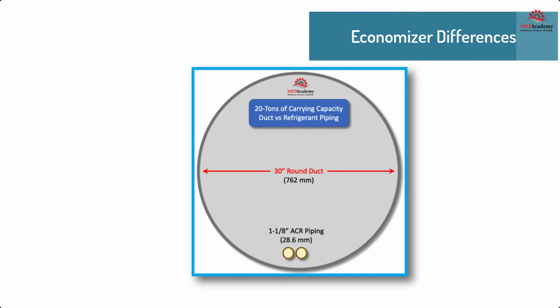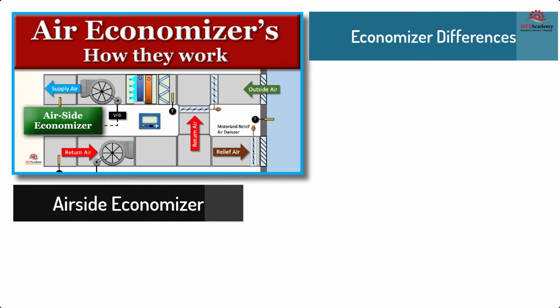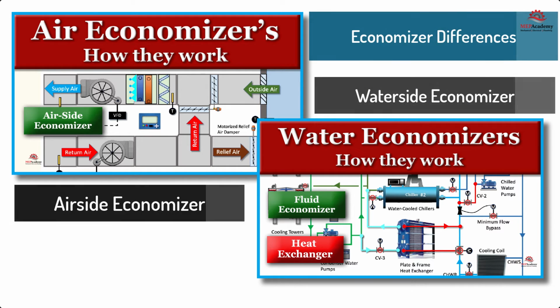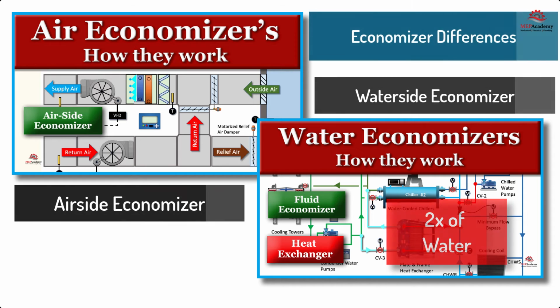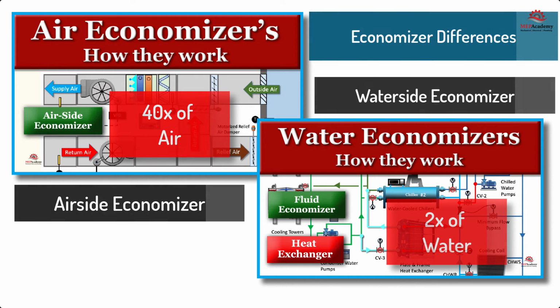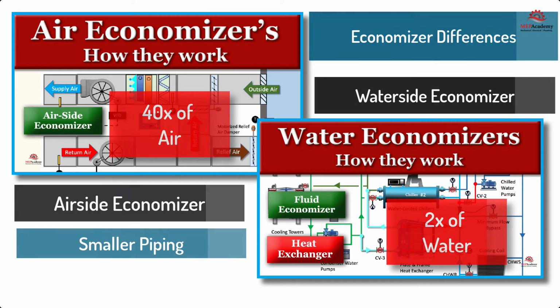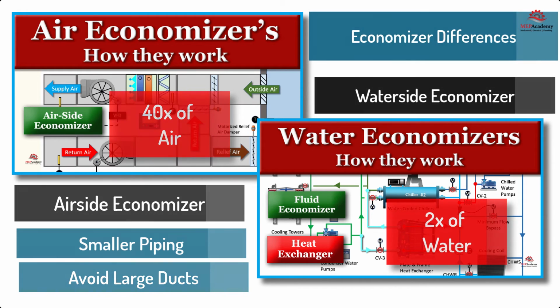Economizer differences. Refrigerant allows for greater heat absorption capacity than either air or water. Refrigerant carries as much as 2 times the heat of water and 40 times as much as air. This allows for smaller pipes and the avoidance of large air ducts and contaminated air coming in and out of the building with an airside economizer.